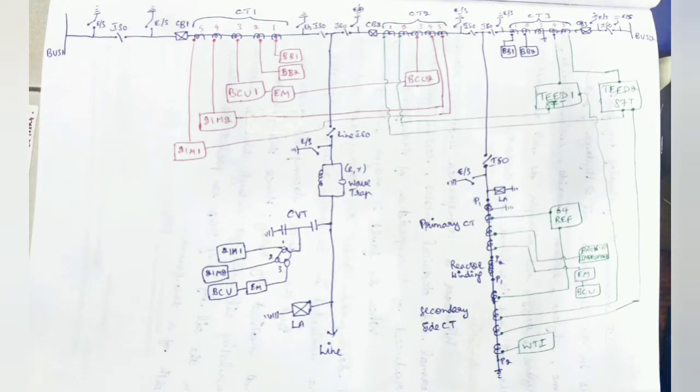The distance relay comprises zone 1, zone 2, zone 3, zone 4 protections, and SOTF (switch on to fault), then breaker failure, and then broken conductor failures, and then over voltage, fuse failure, over current protection, and then power swing blocks.